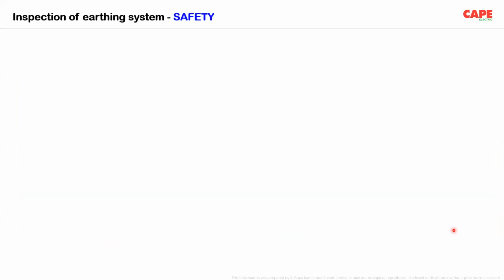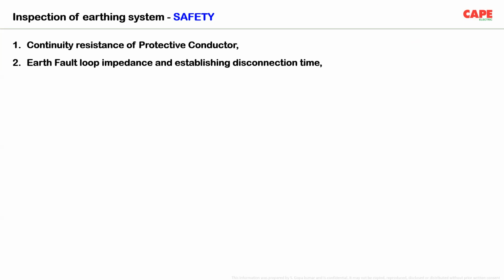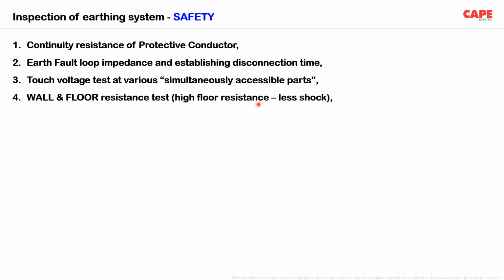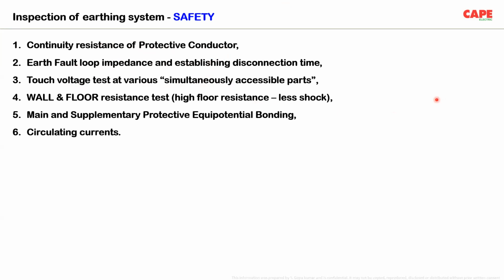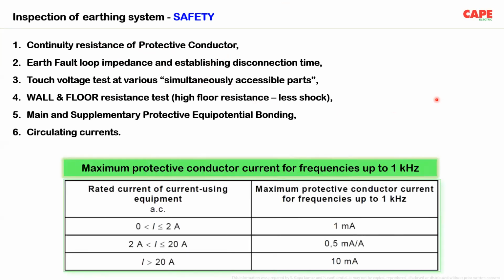So if you want to make a safety earthing, or if you want to make an inspection, then what you should do is measure the continuity resistance of the protective conductor. You should have an earth fault loop impedance and establish the disconnection time. You should have a touch voltage across simultaneously accessible parts, a low value, high floor and wall resistance, main and supplementary protective equipotential bonding. You should have reduced circulating currents. These are the 6 parameters which are related to earthing.